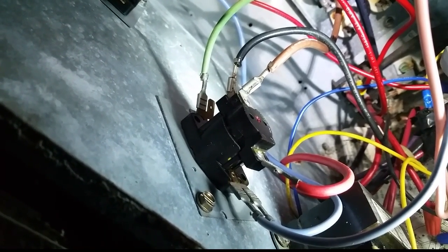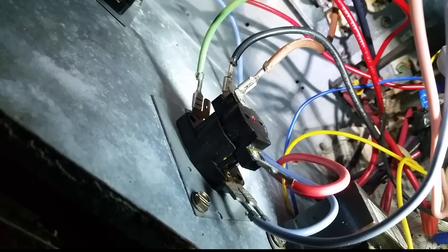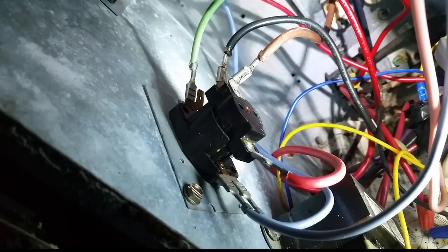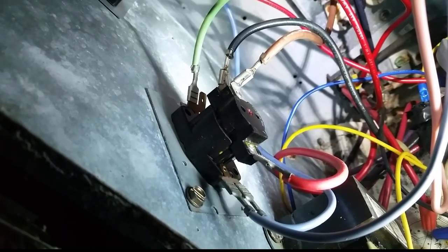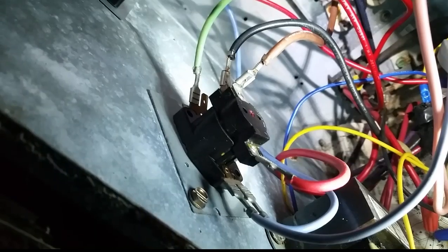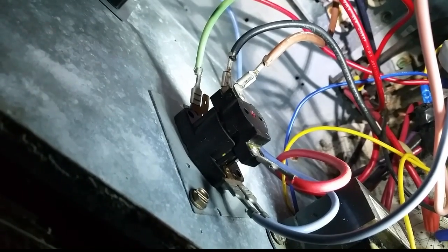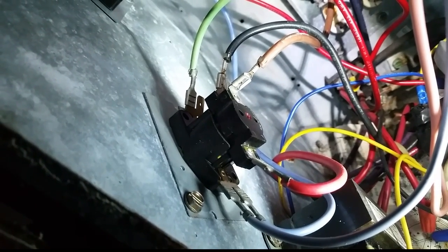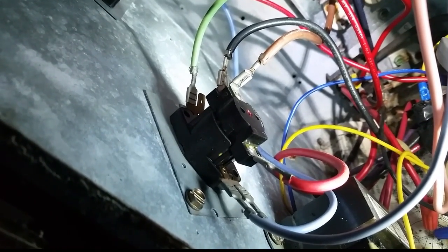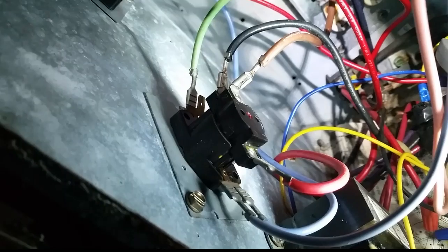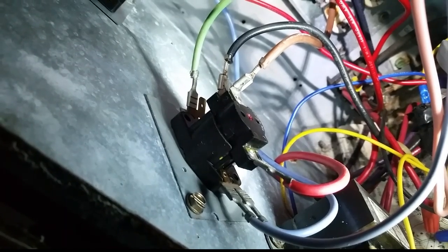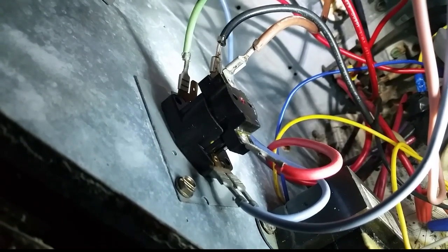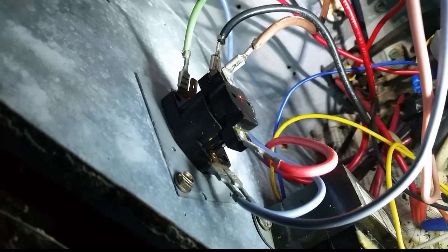Likewise, if you have a call for heat pump, your power comes from the 24 volt fan signal, closes the circuit between the red and black and opens the circuit between the brown and black. So two different ways to get power to the fan motor.